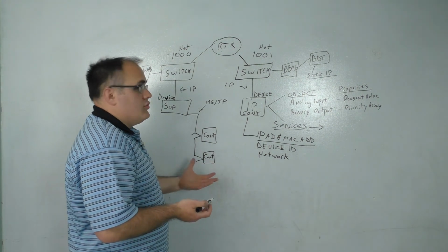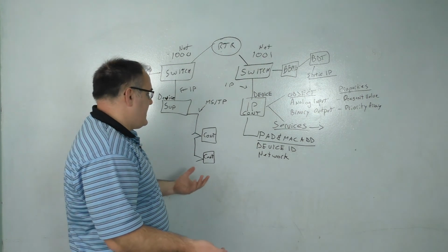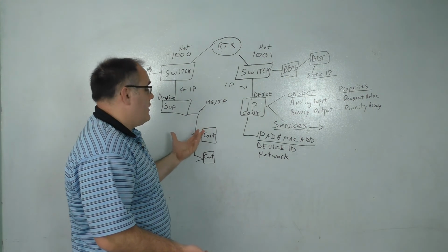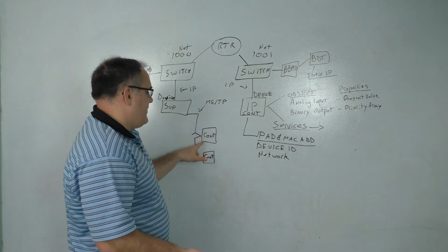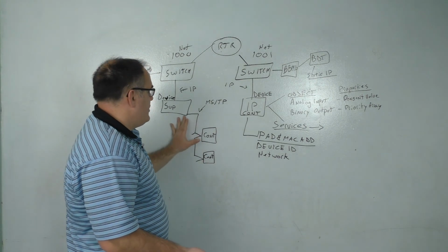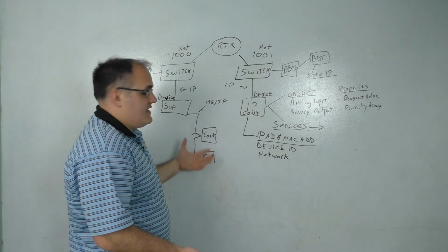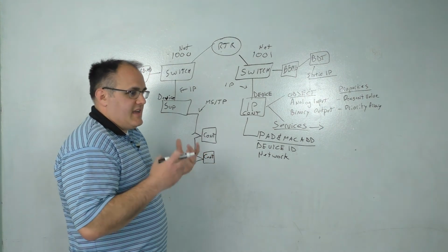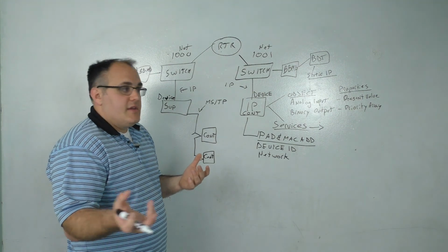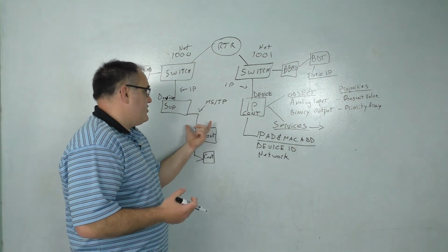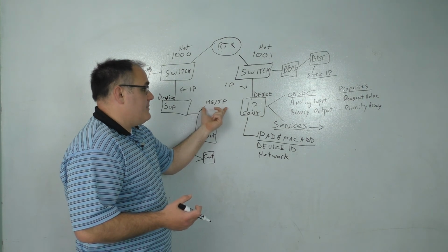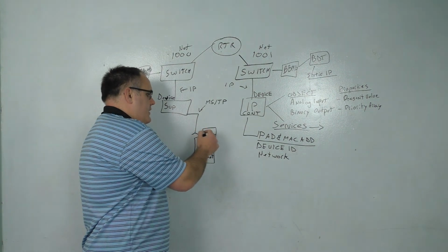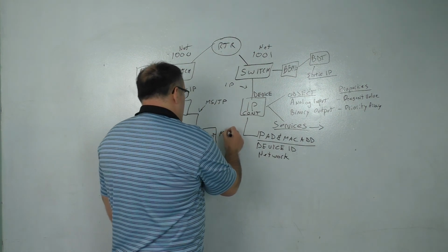And you could then use repeaters to have even more devices on a segment, because basically this would be anywhere from a 2 to 4 wire connection going from a supervisory device to a controller. And then you would have voltage going across these controllers. They would carry what's called a token, which is just a construct. It's like an Ethernet frame. Well, it's a logical construct, and the token is the form of the MSTP message container. That message container travels along the network, and it goes in order of MAC address.